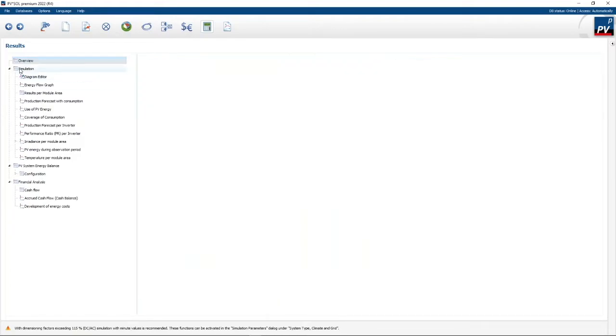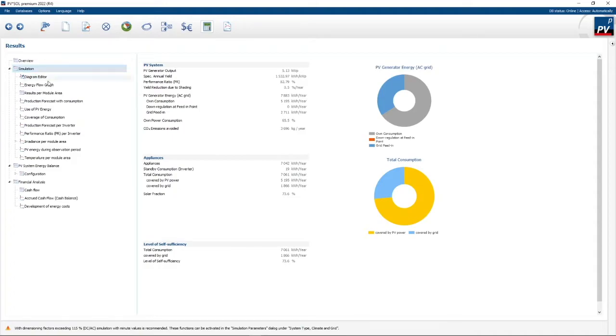If you click on the simulation item on the left, you'll get these graphs. Own power consumption is 65% — in other words, 65% of the PV power you use directly and the rest goes to the grid. Solar fraction is 73% — meaning 73.6% of your consumption is covered by PV, which is your level of self-sufficiency.